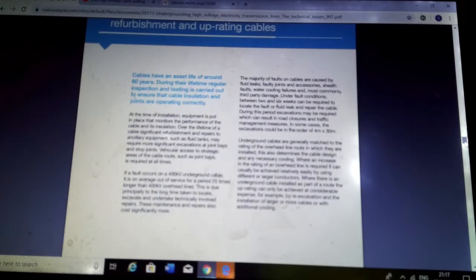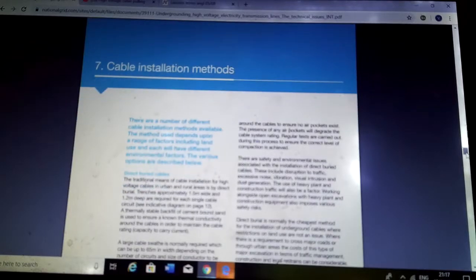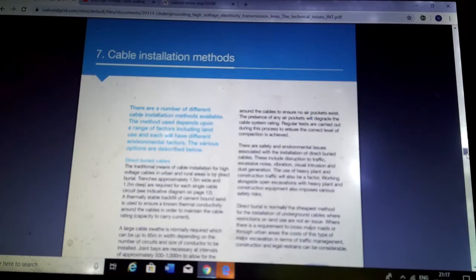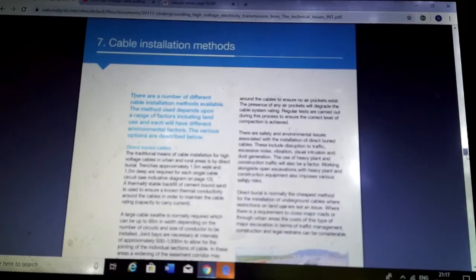So it can take 2 to 6 weeks to locate a fault or a leak in the cable and repair the cable. During this period, excavations may be required, which can result in road closures and traffic management issues. In some cases, the excavations could be in the order of 4 meters by 30 meters. Underground cables are generally matched to the rating of the overhead line route in which they are installed. This also determines the cable design and the necessary cooling. One of the things to remember is that in some cases they cool them by putting a metal pipe alongside the cable, and this absorbs the heat.